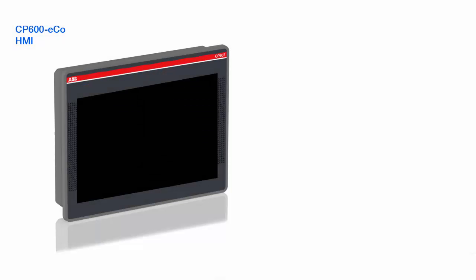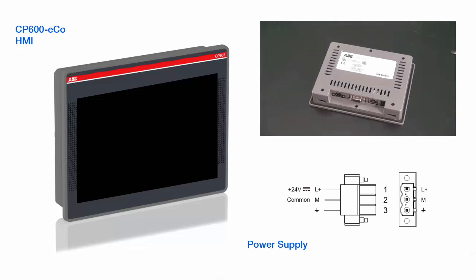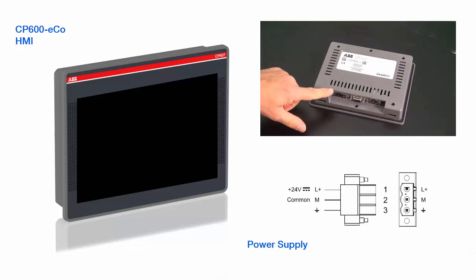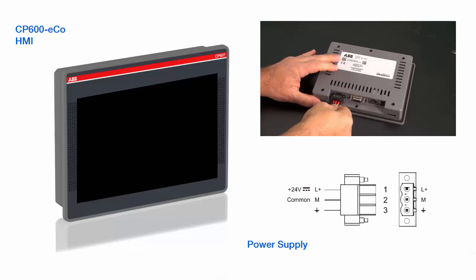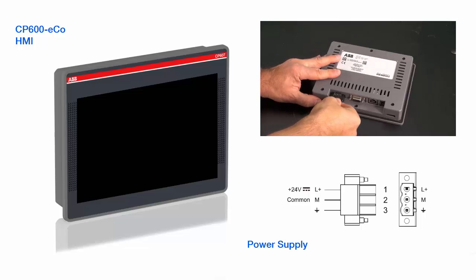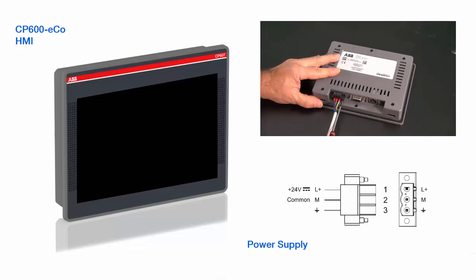At first, the panel needs to be powered by adapted 24 volts DC. Ensure that this power supply has enough power capacity for the operation of the equipment. The panel must always be grounded to earth in order to limit the effects of noise due to electromagnetic interference on the control system. As shown on the screen, use the specific power supply terminal block provided with the panel.